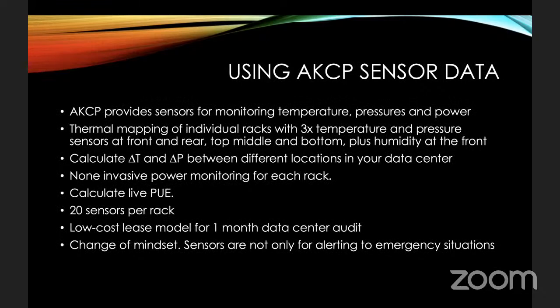You can thermal map individual racks. We have thermal mapping with 3 temperatures at the front, 3 temperatures at the rear, pressure differential at the front, pressure differential at the rear. And we can calculate these delta T's and delta P's around the different locations in your data center. We have non-invasive power monitoring as well. So this allows you to also check your PUE numbers. So as you make changes to the data center, you can see how it affects everything. What we have to remember here is that a data center is a dynamic, living, breathing machine. And you should be aiming to constantly tune the data center for optimal efficiency.